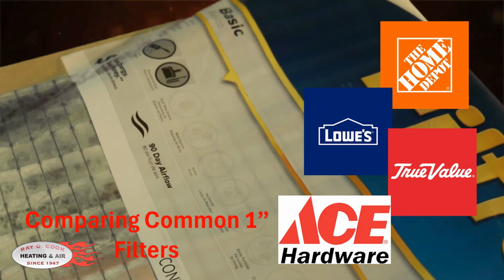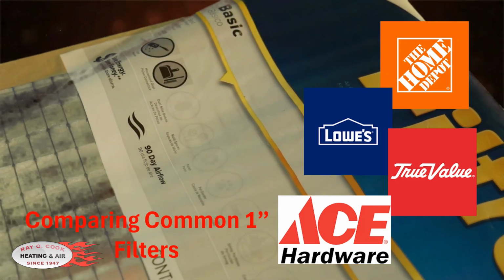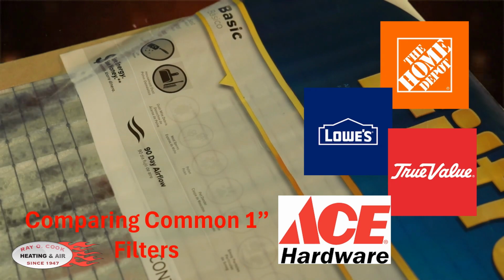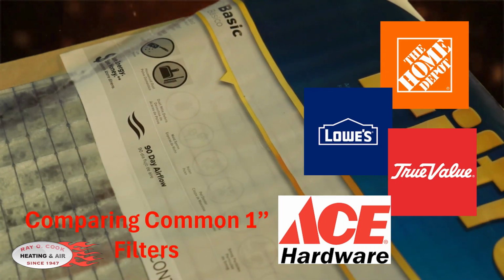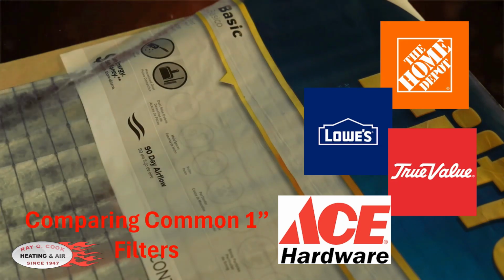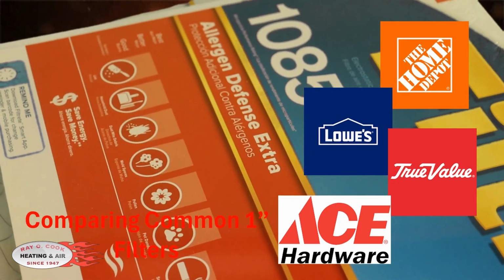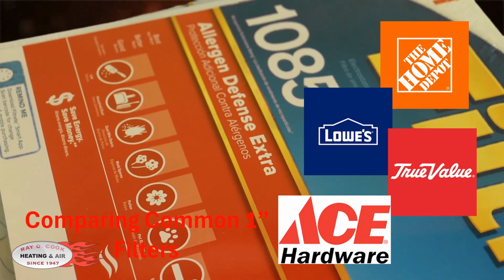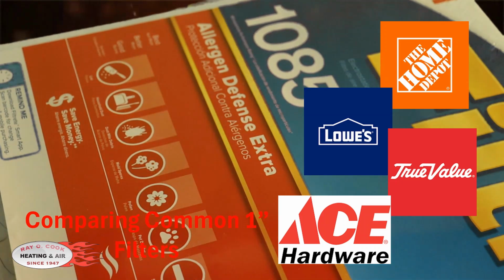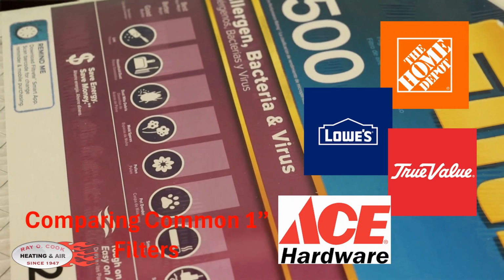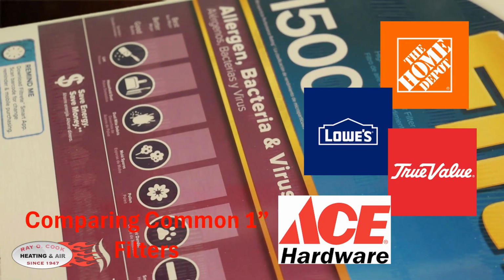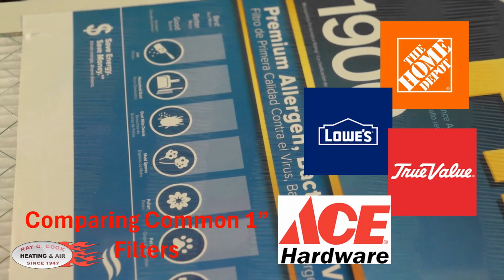And this particular manufacturer calls this their basic filter. The next one is going to be colored red, and it says right on it that it is a MERV 11. And this manufacturer says that it's Allergen Defense Extra. And the next one up would be a MERV 12, and this manufacturer says that it's allergen, bacteria, and virus.